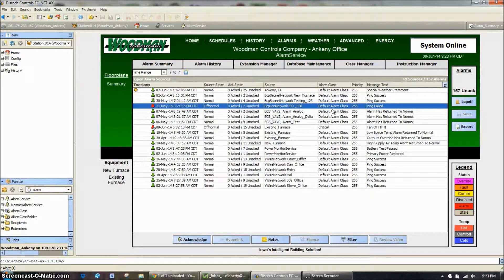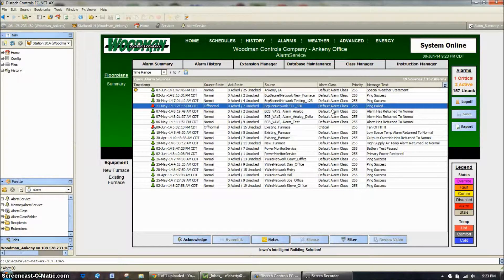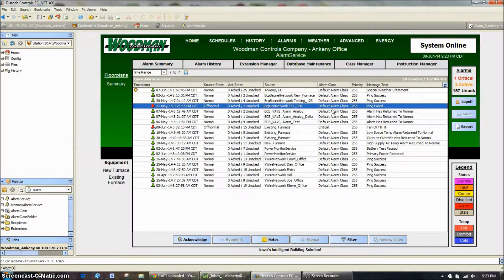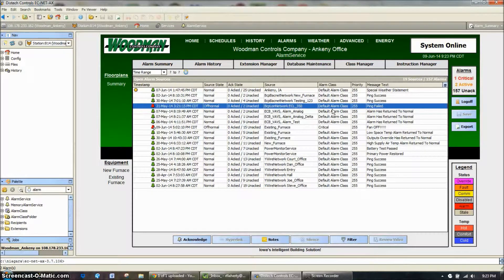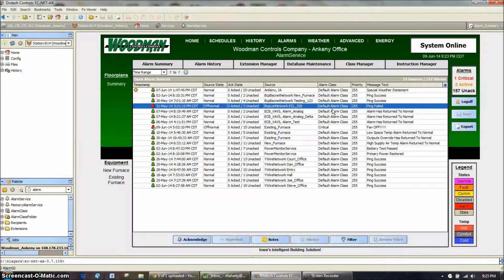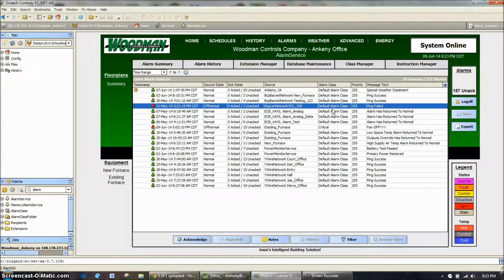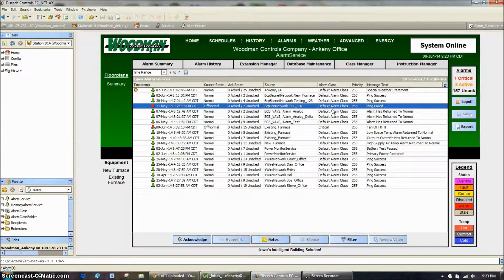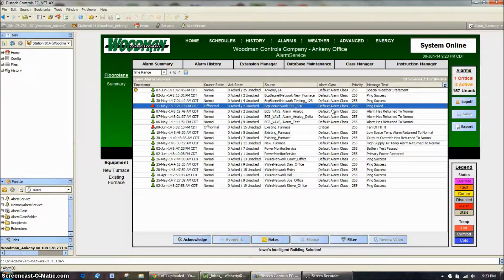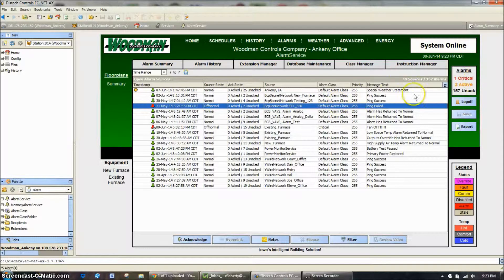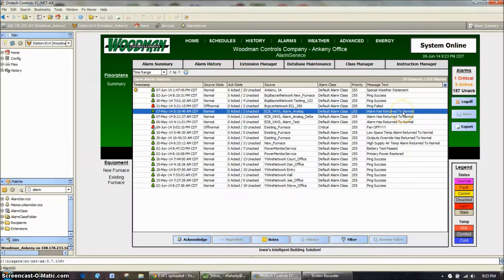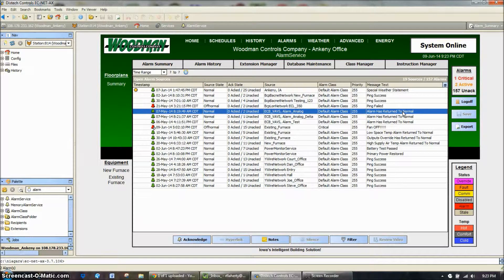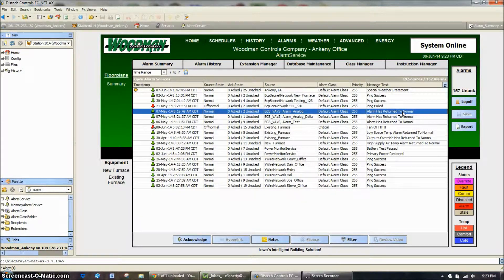If it's critical, that's usually something that's critical and we really want to know about it. I don't have any critical alarms here now, except for one we made up in a previous training class called Fan Off. That critical alarm is just showing that the fan has turned off. And then the message text, so however you have set up your alarm, or how we have set it up straight from Woodman before you got it, alarm has returned to normal, or ping failure, ping success, those are usually due to controllers going on and offline.